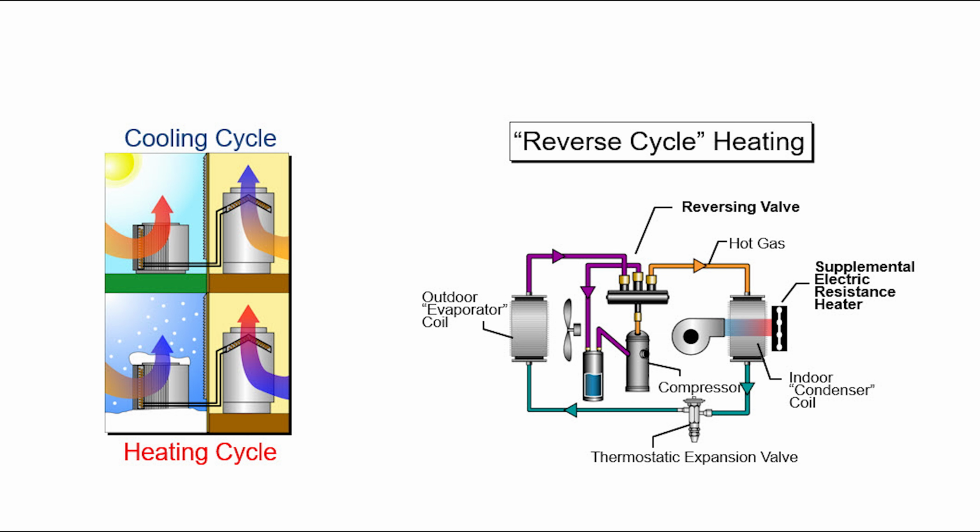When you have a heat pump, what ends up happening is the condenser coil and the evaporator coil switch jobs. You can think of it as if I picked up that outdoor unit and brought it in and set it in the middle of your office building, and I took the indoor unit and set it outside. Those things are not smart enough to know that I relocated them, so they would keep doing their current job, and one would absorb heat outside and the other one would reject heat inside.